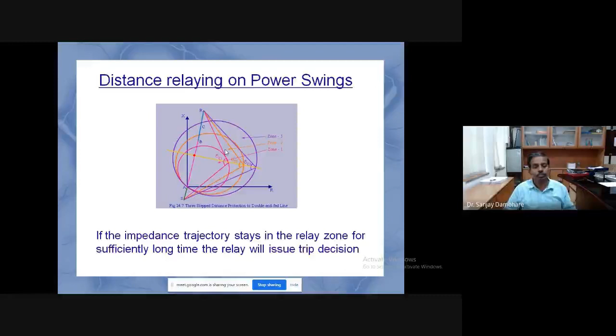So these are some simulated voltage and current waveforms, showing how the voltages and currents look during the power swing. You can see that power swing is a transient phenomenon. The system is under swing, and during the power swing, when the voltages are less, the currents are high. So it may be in this particular region of the impedance trajectory. But when voltages are less and currents are high, the relay will take it as a fault, because voltage is less and current is high.